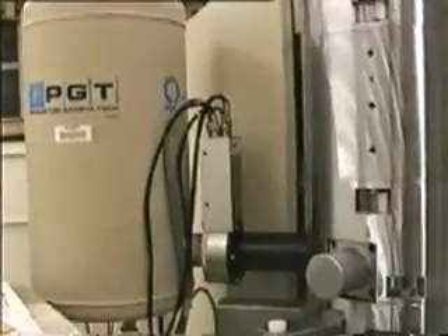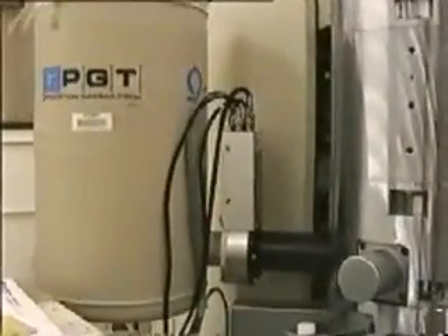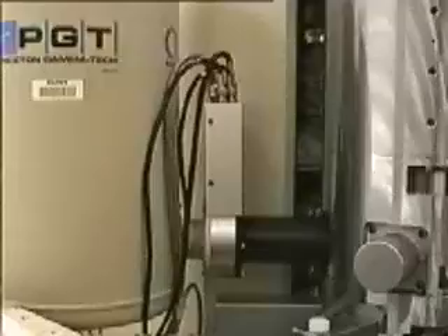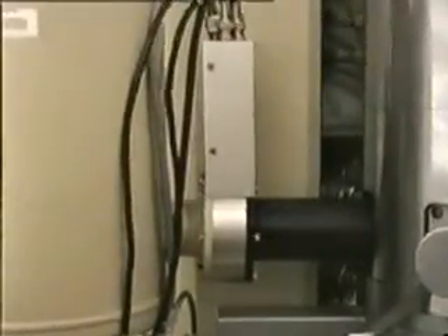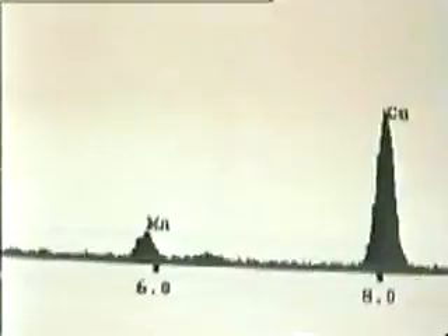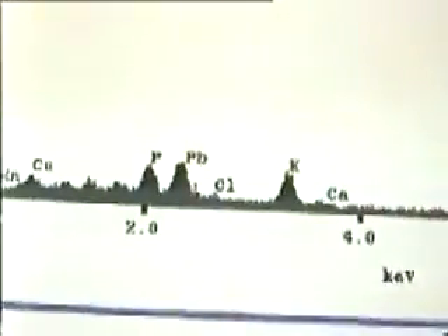The scanning electron microscope may also be fitted with a detector for X-rays. Here, a large canister of liquid nitrogen is used to cool an X-ray detector assembly fitted into the specimen chamber. When beam electrons strike the specimen, X-rays of different wavelengths and energies are emitted, which, when captured, are used to generate a series of peaks, each representing elemental information. Thus, while making magnified observations of the specimen, its elemental composition can be determined electronically.